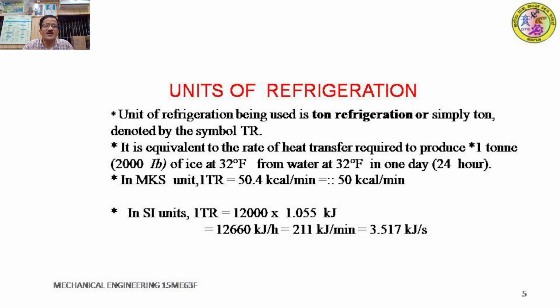In MKS units, 1 ton means 50.4 kilocalorie per minute, or you can round it off to 50 kilocalorie per minute. In SI units, International System of Units, 1 ton of refrigeration is given by 12,000 into 1.055 kilojoule, that is 12,000 British thermal units.